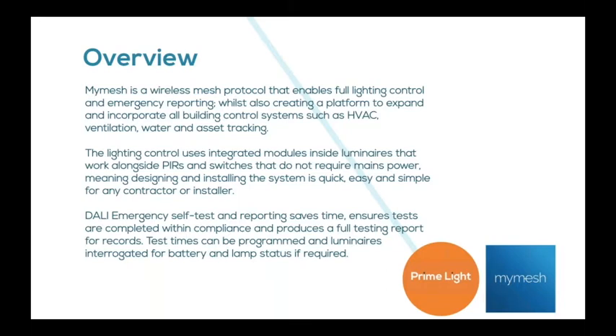The way it works with luminaires is that you have a module that you integrate into your light fitting or external to the light fitting. That wires into your driver - on/off, 1 to 10 volt, DALI, etc. - and controls that to either dim or turn off the light. Then we either have plug-in PIRs, microwave sensors, or externally mounted PIR sensors and switches to control those luminaires. So it's incredibly easy to design into a solution, install, and then specify as well.